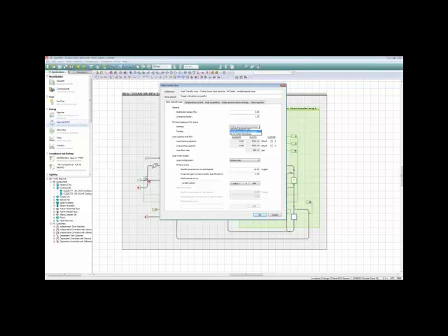Then we have some new facilities for the sizing of the capacity on the loop, so we can go with auto size values. We have a current default value. We can override the auto size values and put in our own values and maintain the auto size values, so we have more flexibility with how that works. Again, the black A next to the dialogues means that these values have the potential to be auto size. And we display the loop flow rate down below that's associated with those values.